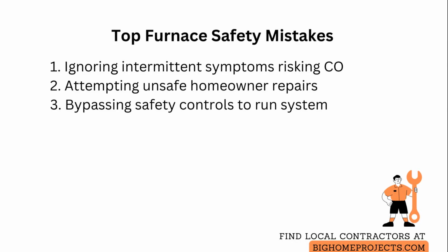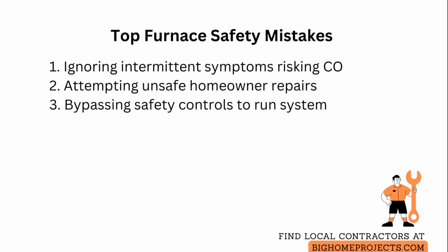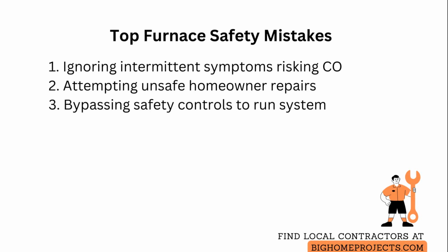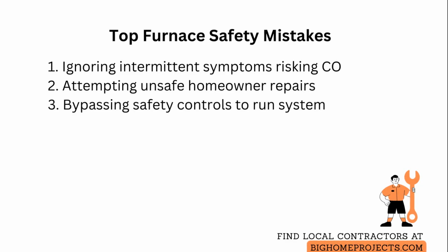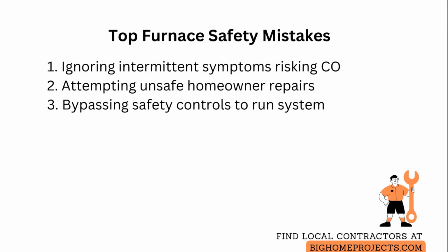A third frequent concern is bypassing safety controls like flame rollout switches to keep the system running. That overrides protections designed to prevent fire and poisoning. So never bypass or tape over switches, and always rely on proper diagnostic procedures and component replacement.